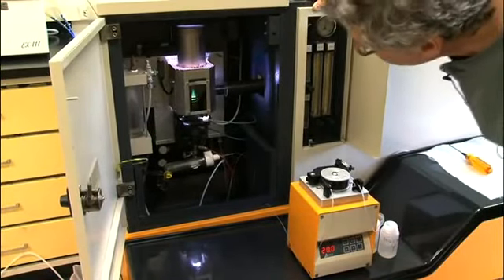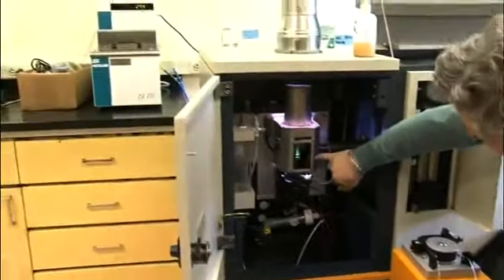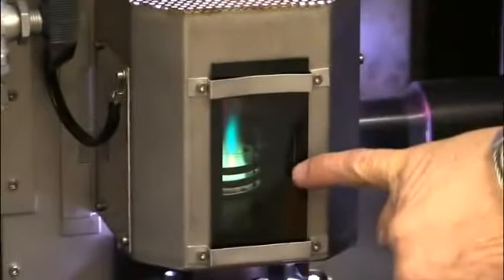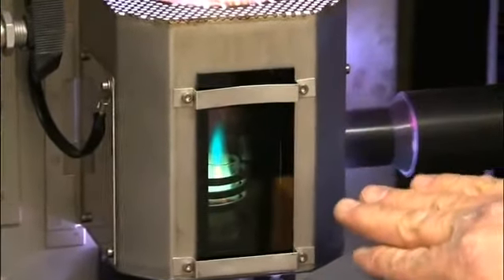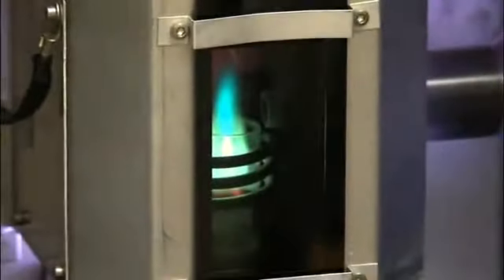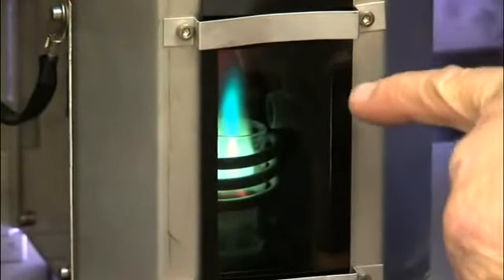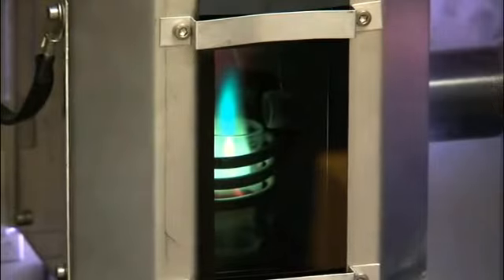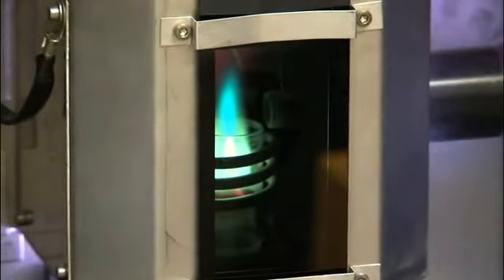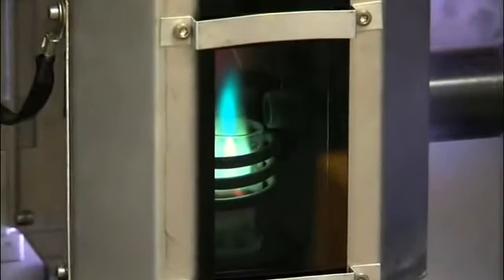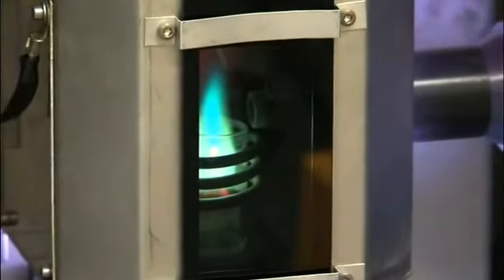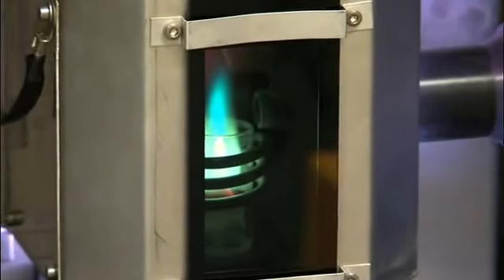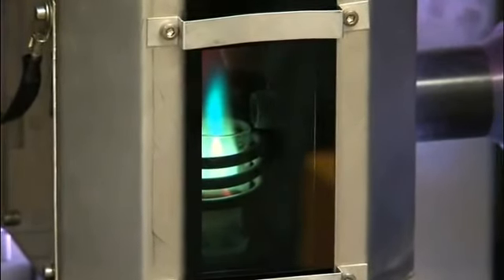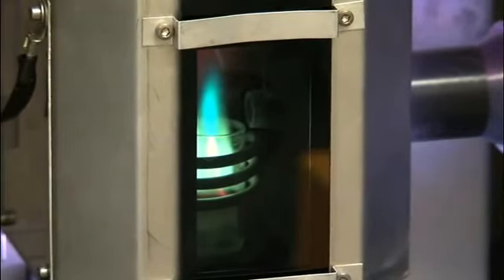Okay, so what we're looking for is, if you see what we call the tip of a bullet, the orange part below the blue, that should come up 1 to 2 millimeters above your top coil. Most of your light emission takes place theoretically in the middle of the blue zone, which is what this should be looking at. If I bring this down, you'll see it come down. So that adjusts that nebulizer pressure directly. So right now is about where I had it. It's about 2 millimeters above the top coil.